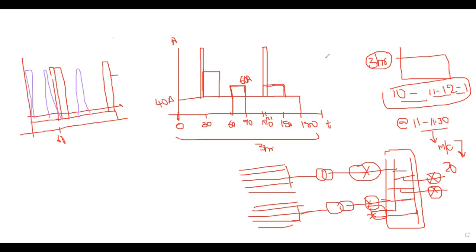So you can decide what battery you want, 220 volts battery or 110 volts battery. Even for our telecommunication purpose, we are using a 48 volts battery also. So it totally depends upon your requirement, whether 220 volts, 110 volts or 48 volts. 48 volts is generally for PLCC communications or FOTE communications, dedicated. And for 220 kV, the 220 volts battery is widely used across all the substations. Again, this is just a fundamental kind of selecting the battery.